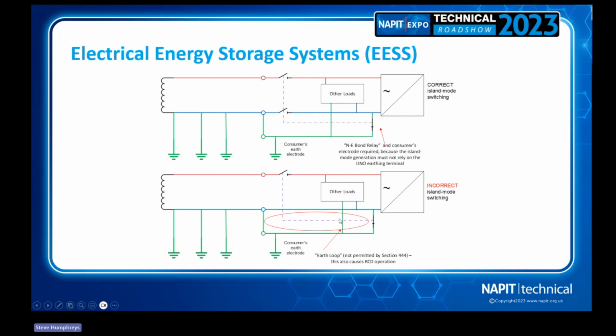And then you can see where that's been done incorrectly, because what we've got here is the neutral hasn't broken in this instance. We've created almost circulating neutral currents, which is a possibility because we've got two points of neutral bonded to earth, and this is not permitted. This can cause RCDs to go doolally and all kinds of weird and wonderful things as well.